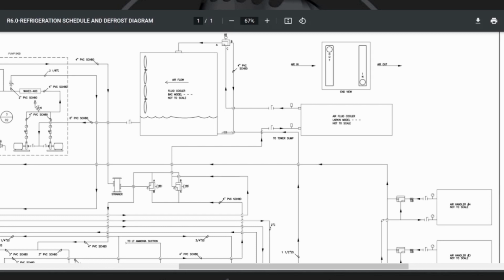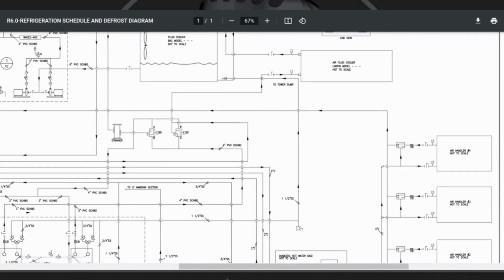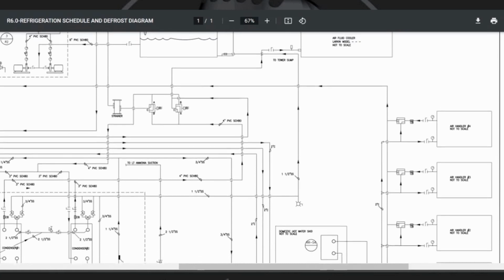and our EER on the mechanical system. And even though you fill out an RS sheet and you got 1.7 million BTUs heat load, that only occurs on a design degree day. And even that, in our experience, you never get to that rated load. That's taking the case manufacturer's load and the walk-in box manufacturer's load, and you add them all and the air conditioning load. Well, none of these loads are all running at the same time. It never happens.